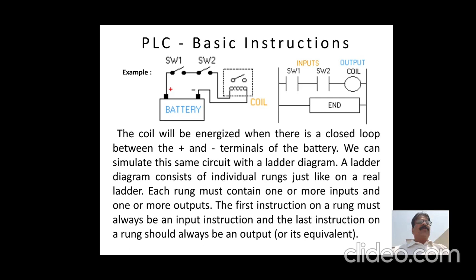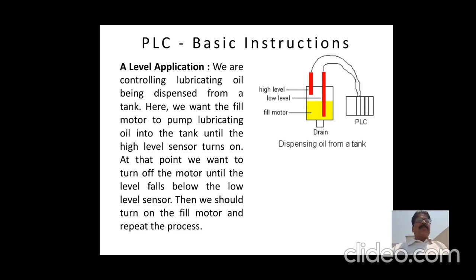See one more example to understand the basic instructions of PLC. This is a level application. We are controlling lubricating oil being dispensed from a tank. Here we want the fill motor to pump lubricating oil into the tank until the high level sensor turns on. At that point we want to turn off this motor until the level falls below the low level sensor. Then we should turn on the fill motor and repeat the process. This is done by using the ladder diagram.